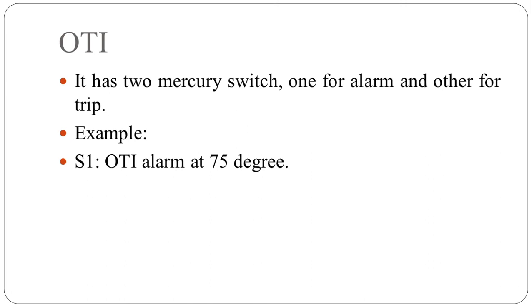In that case alarm circuit gets activated. But if temperature rises further then switch 2 gets activated. Suppose it is set to operate at 90 degree. If temperature exceeds 90 degree then OTI trip signal activates. In that case trip signal goes which isolates the transformer from the supply. So in this way these switches work.